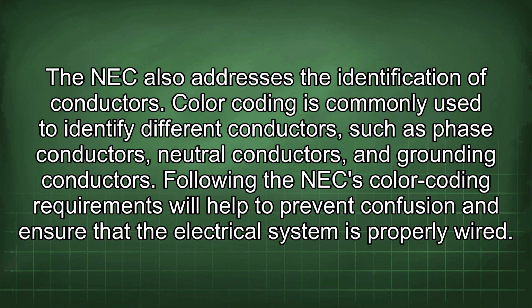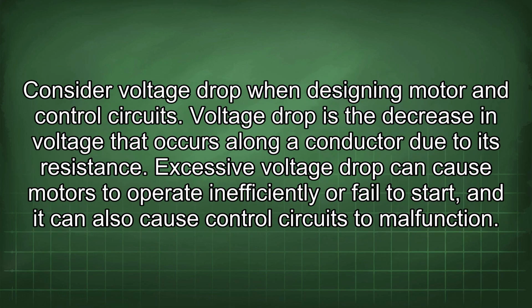Color coding is commonly used to identify different conductors, such as phase conductors, neutral conductors, and grounding conductors. Following the NEC color coding requirements will help to prevent confusion and ensure that the electrical system is properly wired. Consider voltage drop when designing motor and control circuits. Voltage drop is the decrease in voltage that occurs along a conductor due to its resistance.